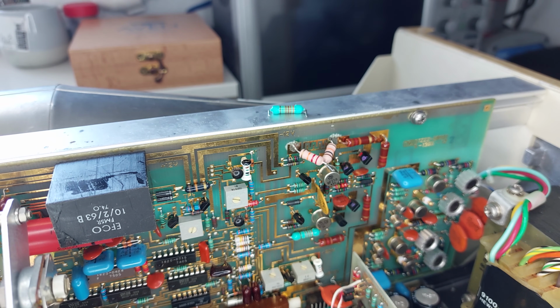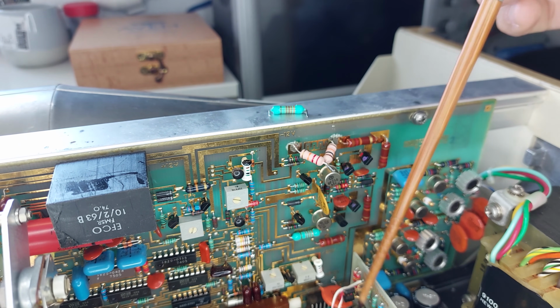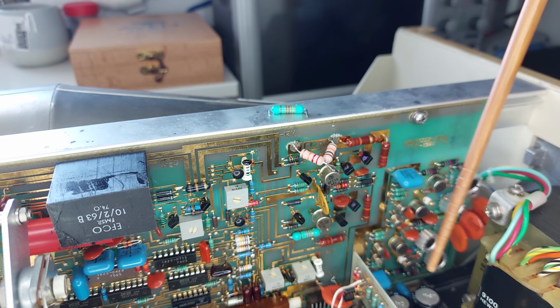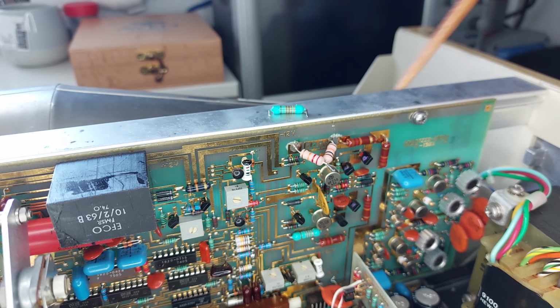When you have a beam that's sweeping a bit slower, slower than a millisecond per division, you can see some modulation in the beam intensity, which means, to me, there's something wrong with the power supply. Now, how do we know there's something wrong with the power supply? Well, the rest of the thing works fine, but there might be something wrong with either of the power supplies. So first of all, with the low voltage power supply that we have here, or the B plus supply.